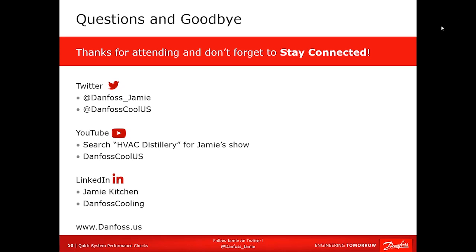Thank you, guys — I appreciate it, especially those of you who've been with us for this whole series. Now for Q&A. First question: how do I know the system is dehumidifying correctly? Generally, you measure the wet bulb and dry bulb off the coil in your supply, measure the airflow, and use the formula for total heat or latent heat and do your calculations. Or if the manufacturer provides a set of conditions, match those — they know how the system should operate under a given set of conditions. A lot of times the reason you're not dehumidifying properly is due to the airflow side.